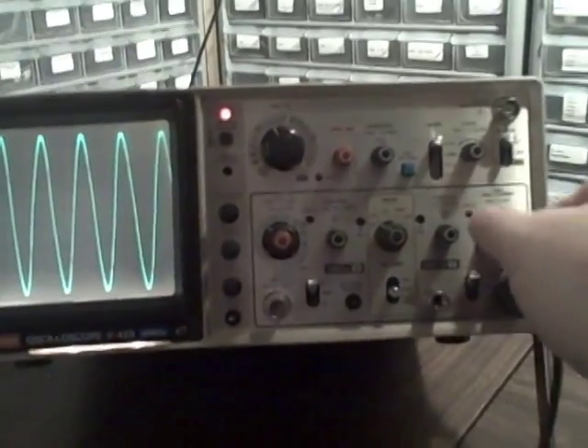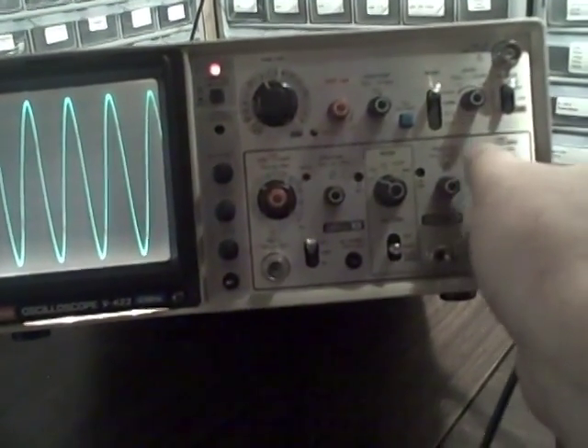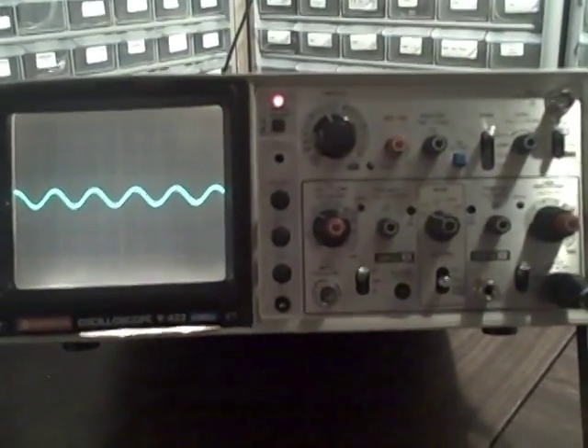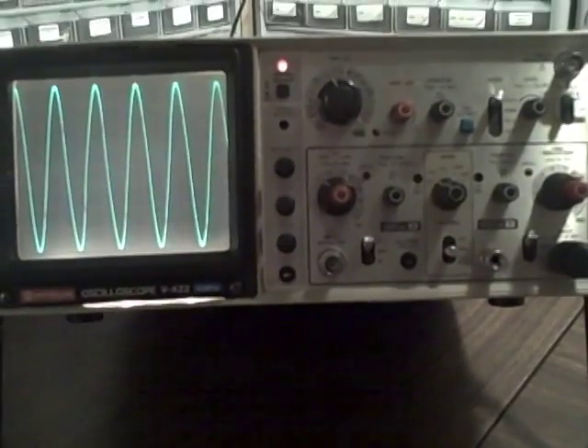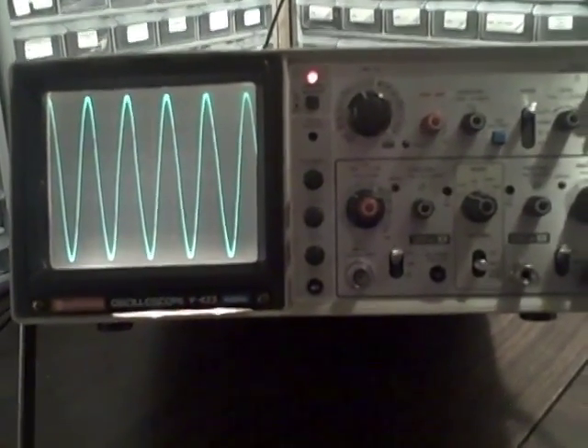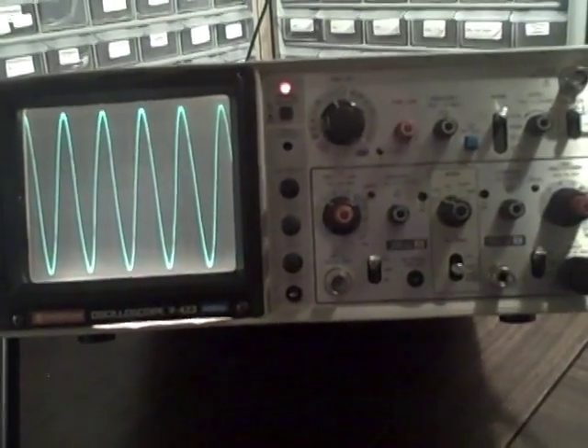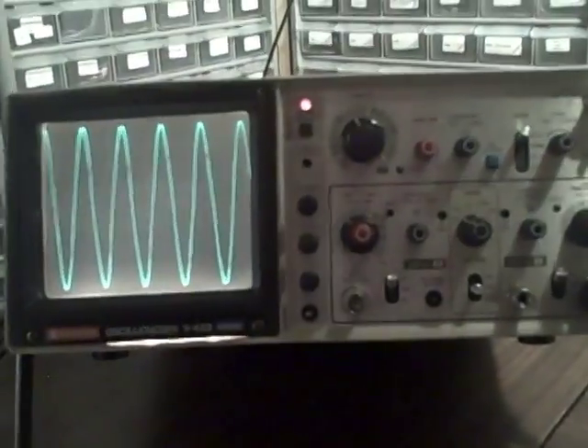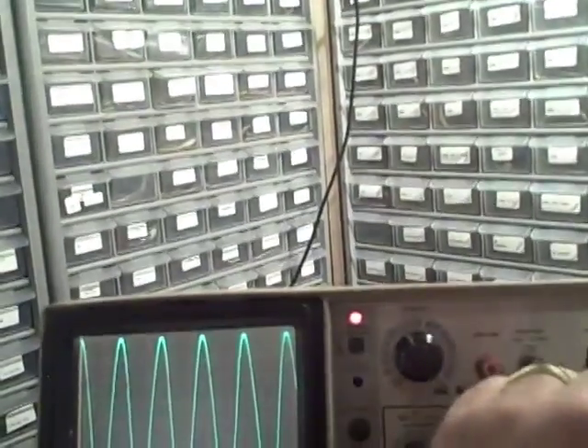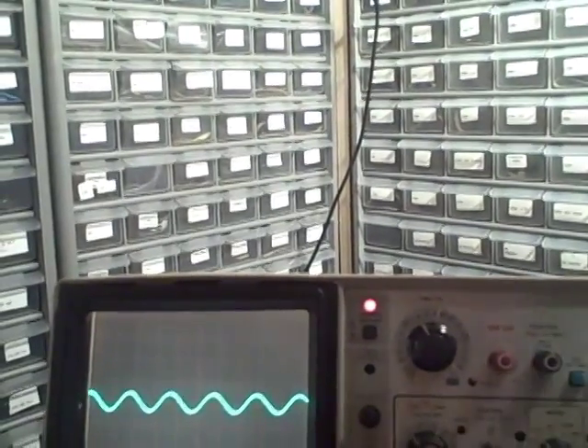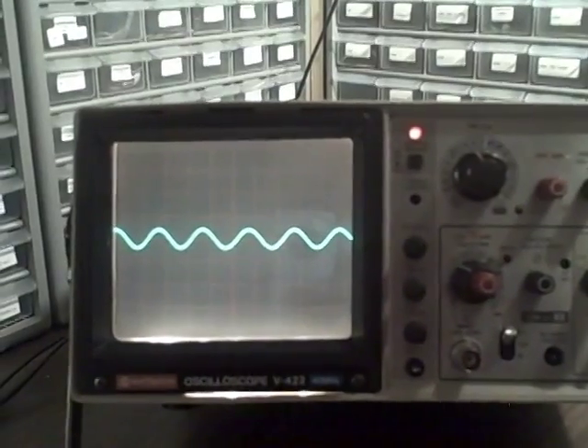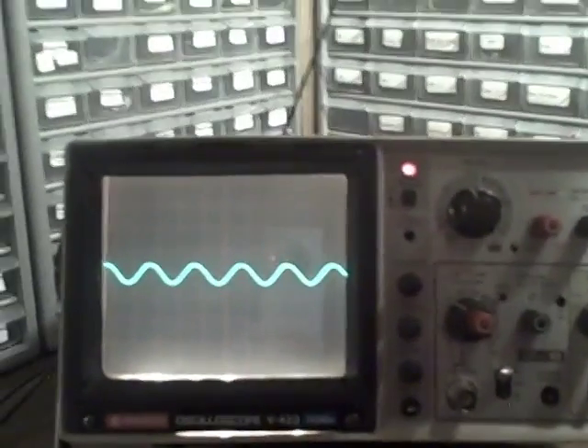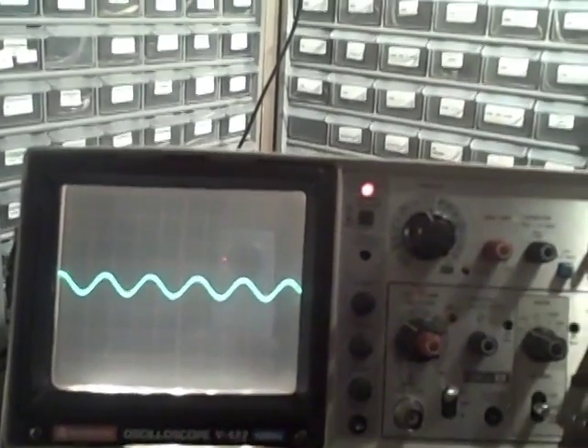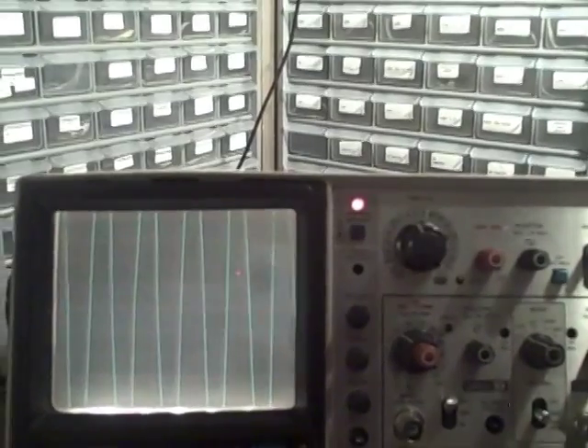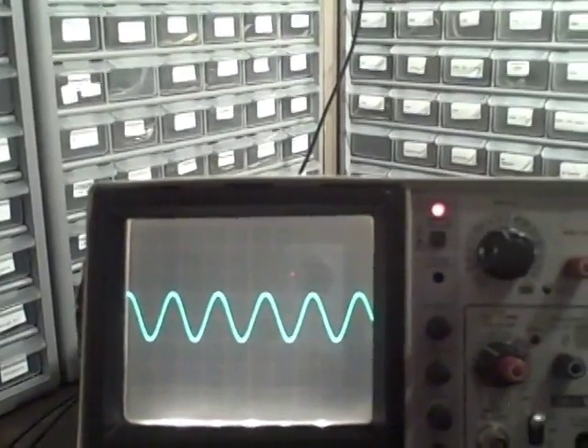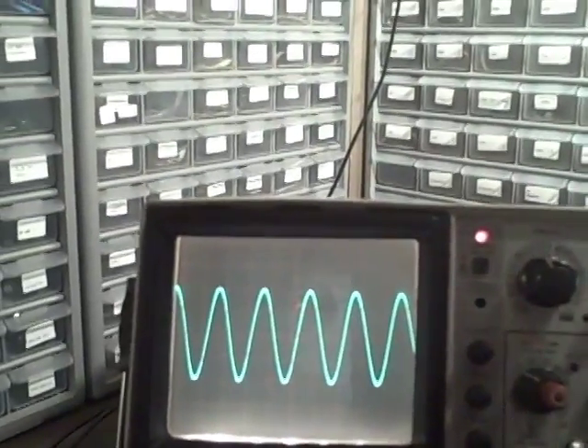Let's go ahead and put ourselves on 50 millivolts per division and take off our divide by 10, and we see ourselves go full scale again, which is as it should be. So we are reading, in this case, 50 millivolts per division, 200 millivolts. Okay, and then let's go up to 0.5 per division, and we see ourselves fall to plus or minus 0.4, which would be 1/10 of the 4 divisions up and down we had before, so that would be correct. Now let's take ourselves back down, put ourselves on divide by 10. We're down to the 10 millivolt per division range.